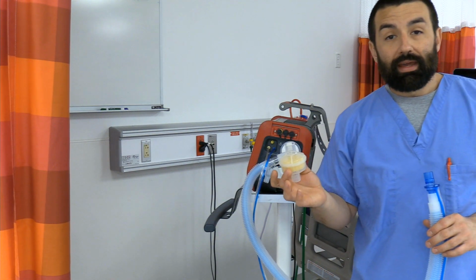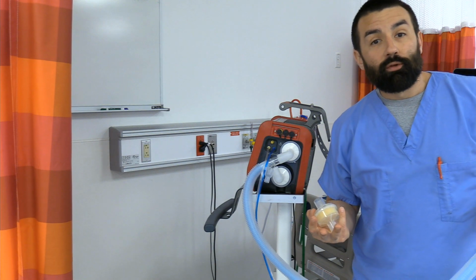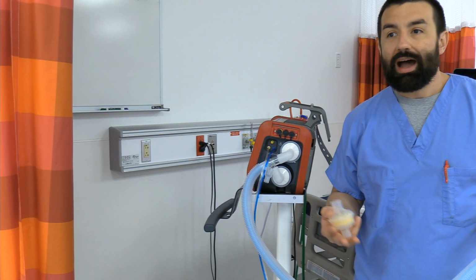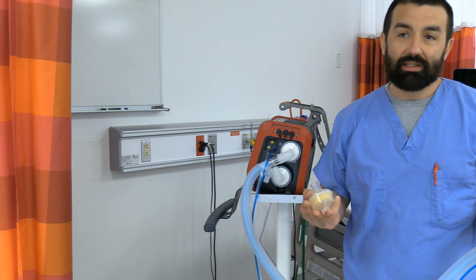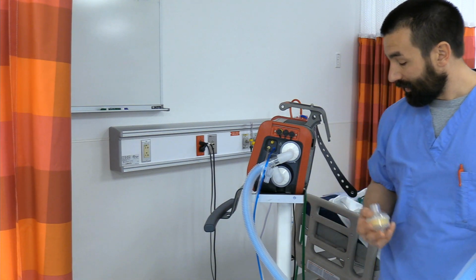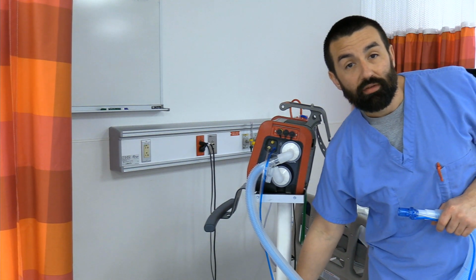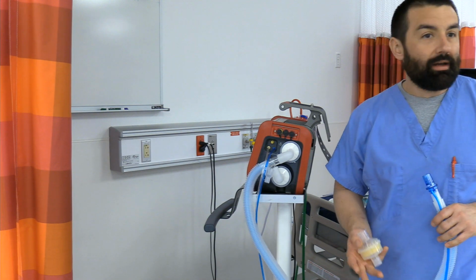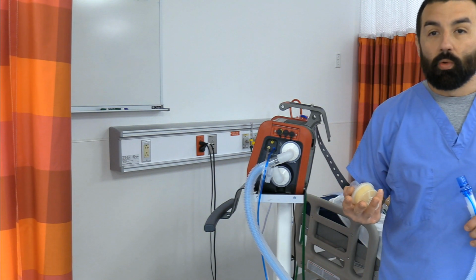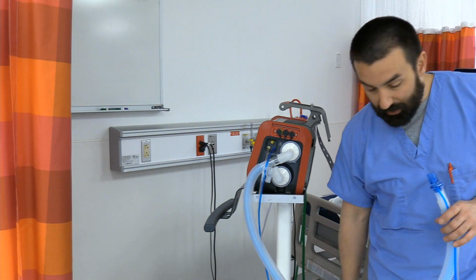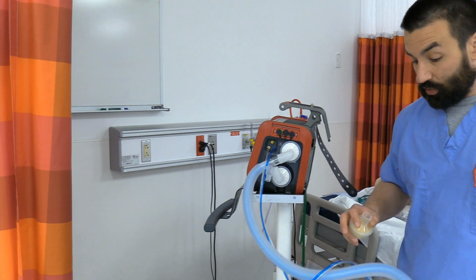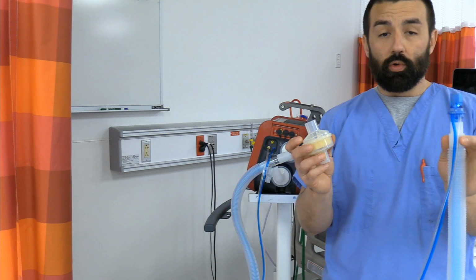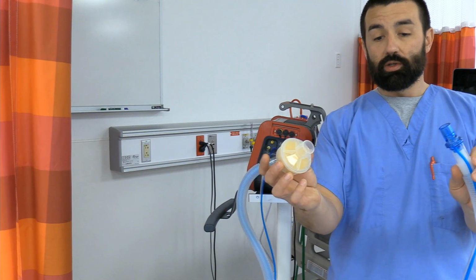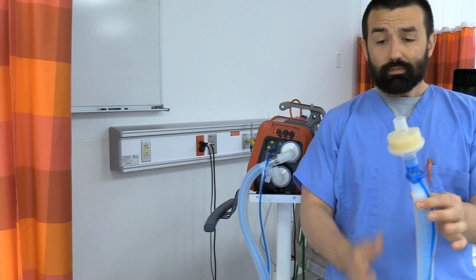Don't overlook humidification. So if we're using this for a patient for a longer period of time, or we're doing high flow oxygen, or non-invasive, you want to add on a little bit of humidification. There is a heater bracket on the front of this, compatible with Hamilton's heater system, or Fisher-Paykel. It's got a standard heater bracket on the front, and you can do heated wire circuit with this. We're doing just this transport circuit here, so passive humidification.